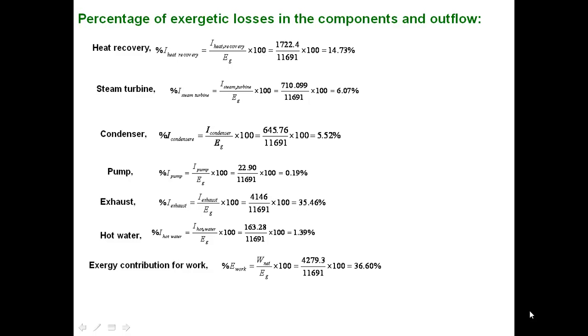Now, the exergy contribution to generate the power is 36.6% which is also equal to second law efficiency. Now, similar to the energy balance, exergy balance also can be evaluated as a heat balance sheet. The total exergy input to the plant is 100% is considered, and the total output is sum of all the irreversibilities plus one component, the last component of exergy contribution towards the work generation. All together, the sum is 99.99%.